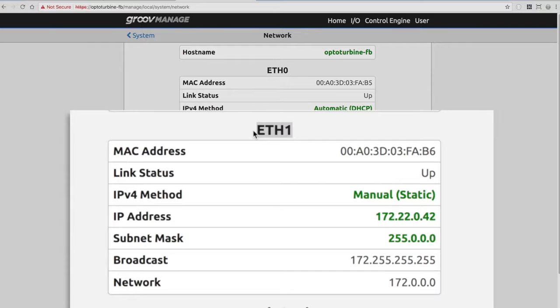Then down here on Ethernet 1, which is the blue cable I described earlier, this one is connected to my OT network, and the Allen Bradley processor is on there. I can see I set up a manual static IP address for that—in this case 172.22.0.42 is the IP address for this Ethernet port. That of course will be on the same subnet as the Allen Bradley controller is configured as well.